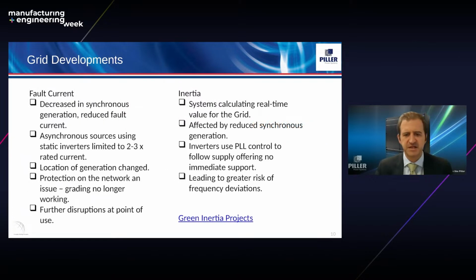So to further combat these issues, Grid is actually adding further services to help with other aspects of the grid now affected by the change in generation sources. Probably the two most significant issues are loss of fault current and reduced system inertia, although voltage issues are rapidly becoming a more significant problem in fact.